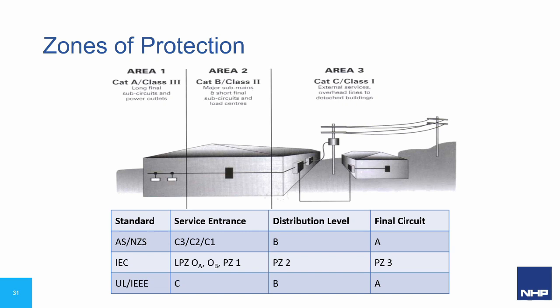The idea of zone protection is common amongst the three standards. Whilst the information is displayed in various formats, standards all seem to agree on the three locations being described as the service entrance, distribution level, and the final subcircuit.